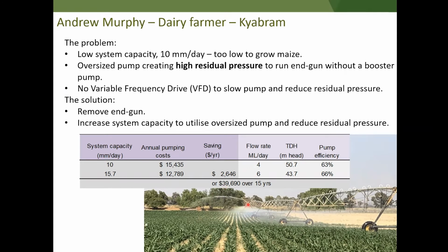And there wasn't much that could be done with the current system. We'll talk about variable frequency drive for slowing pumps down in a second, but Andrew's system didn't have that on it, so there was no opportunity to reduce the pressure at the end. So even by taking the end gun off, the pressure would just stay the same. The pump was still running at the same speed. It wouldn't change operating costs.